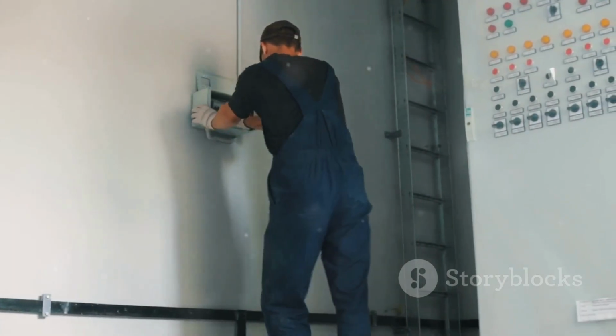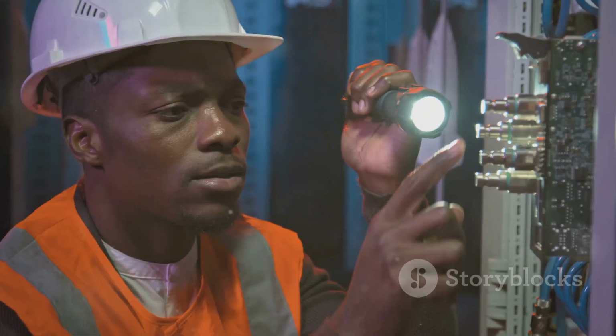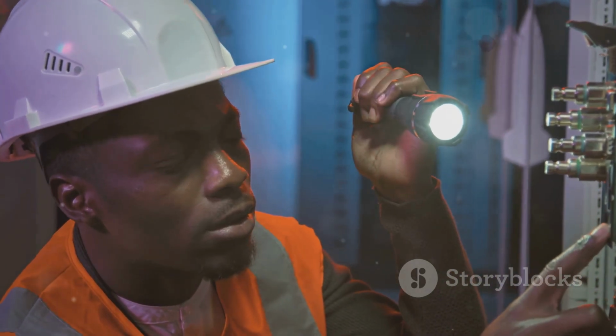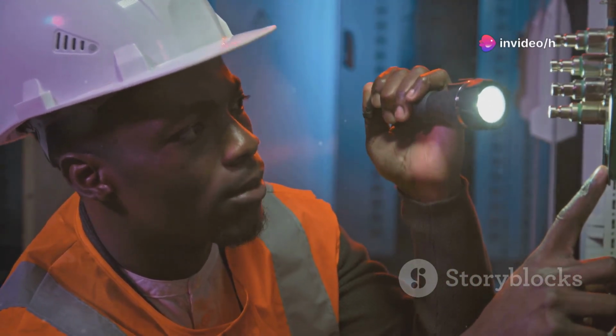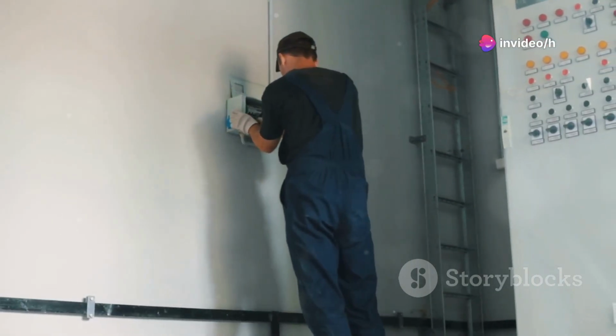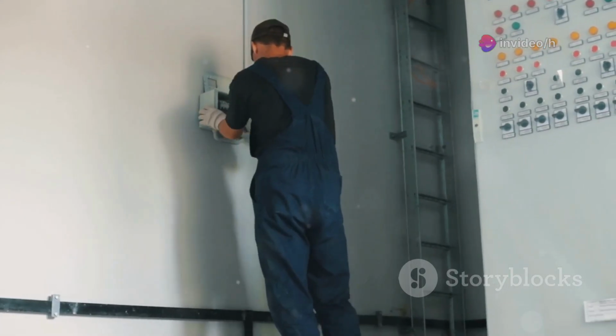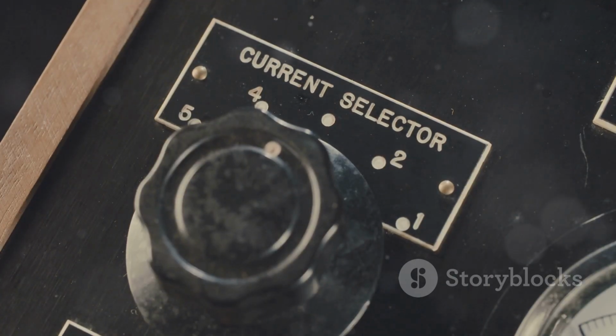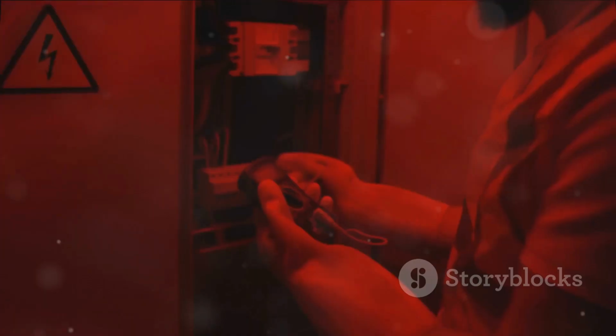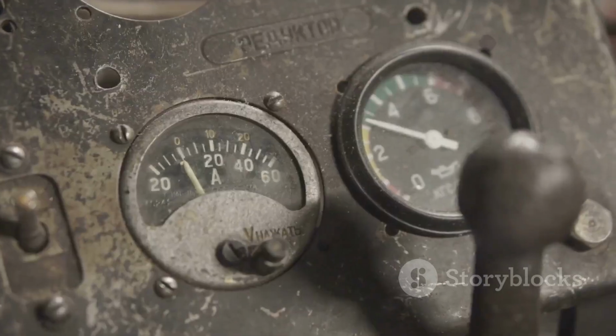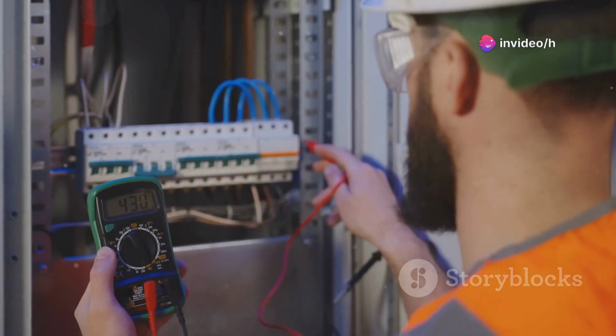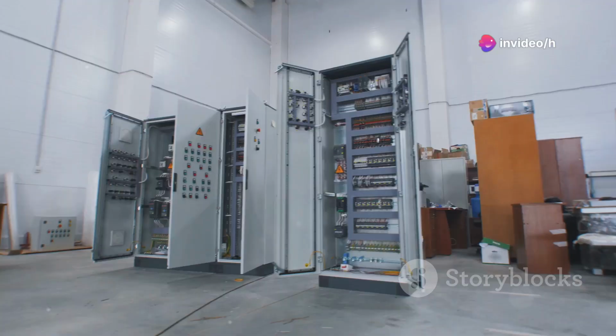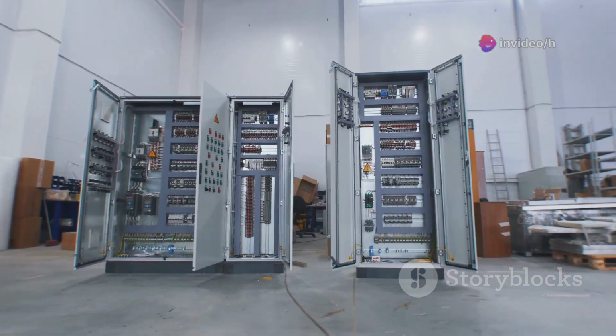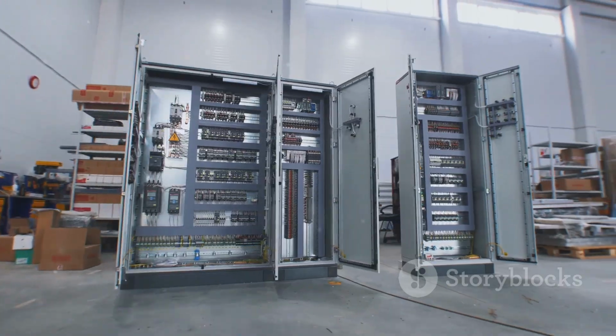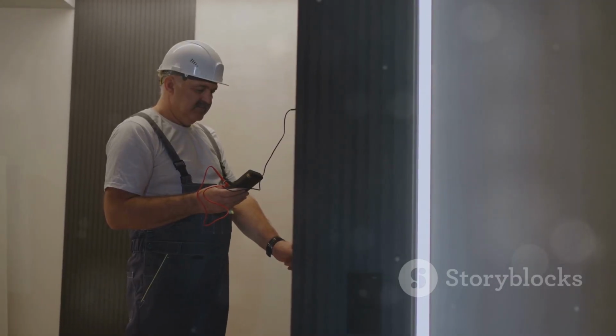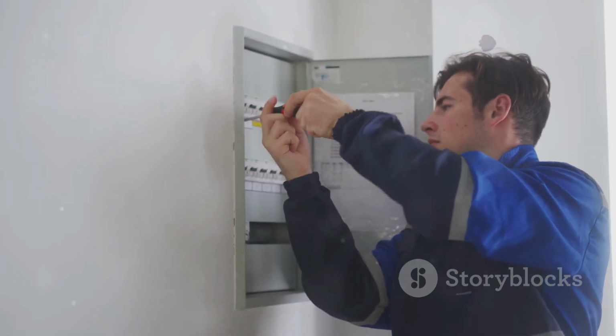Motors need protection from overloads. Enter current controllers. These devices trip if a motor draws too much current for too long, preventing costly damage. Install one controller for each motor right after the MCBs on the DIN rail. Set each controller to match the motor's full load amperage found on the nameplate. Too low and you'll get nuisance trips. Too high and you lose protection. This step is non-negotiable for equipment safety. Together with RCCBs and MCBs, current controllers form a complete protection system. Skipping them is asking for trouble. Protecting equipment is as important as powering it.